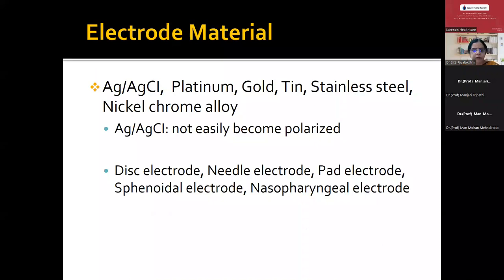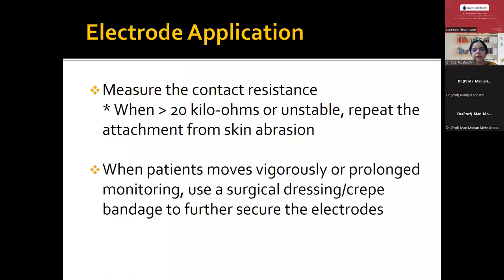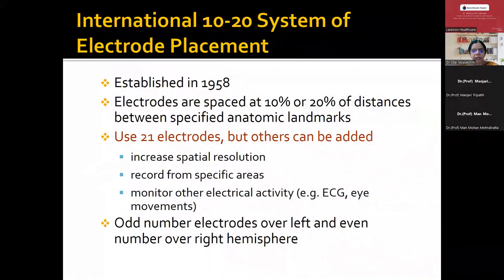Whenever using electrodes — the electrodes are made of usually silver chloride, which are non-polarized. We can use disc electrodes, needle electrodes, or pad electrodes, but most of the time we use cup electrodes. Electrode application is very important — we should always measure the contact resistance once we apply the electrodes. With prolonged monitoring when the patient moves, we use a crepe bandage around the head so the electrodes do not come out.